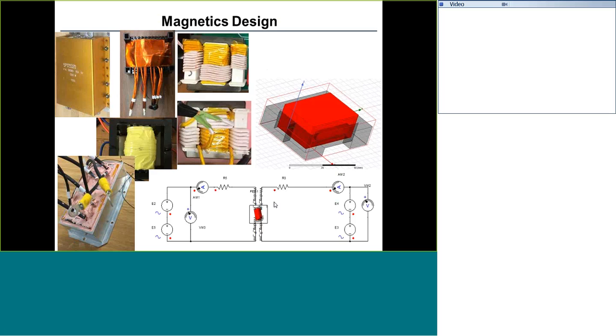One interesting thing we figured out while benchmarking all these transformers is that nearly all the transformer companies provide candidates with pretty low core loss, but the copper loss is usually much higher. So we'd like to ask them to give us as thick copper, or thick lead wire, for the winding as possible to reduce the skin effect.